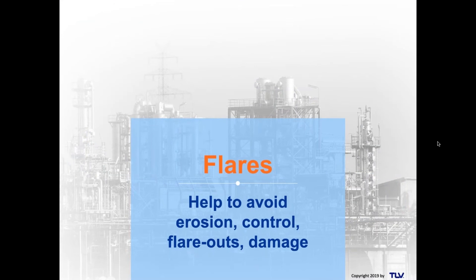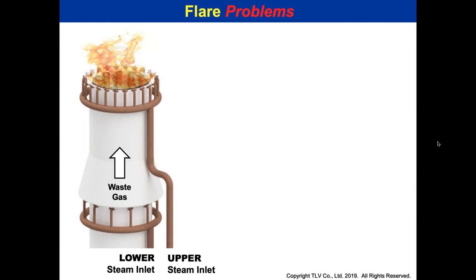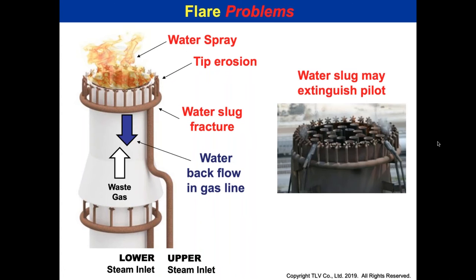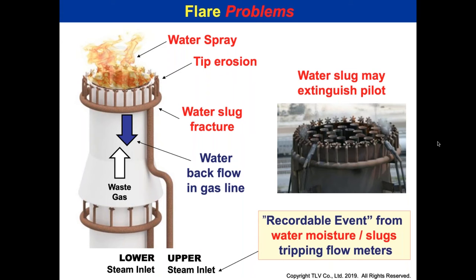We want to help avoid erosion of flare tips, control issues, flare-outs, and flare damage. Problems we've seen include tip erosion, slug fracture, backflow, extinguishing the pilot, water spray coming out — we've used drones and you can see it looks like a water fountain. Recordable events from water, moisture, or slugs tripping flow meters can cost $35,000–$40,000 per event, but they can be avoided. Flares and coker systems are usually far away, but you have to pay attention to those utility lines — they are critical.